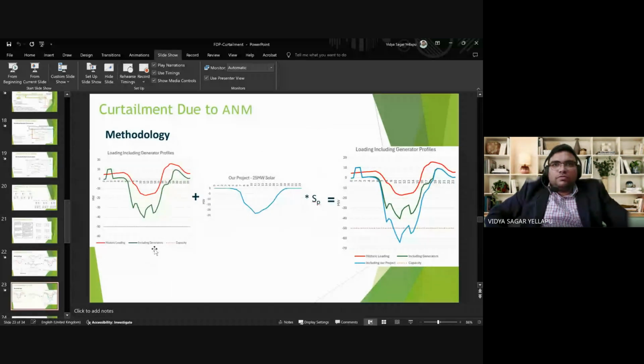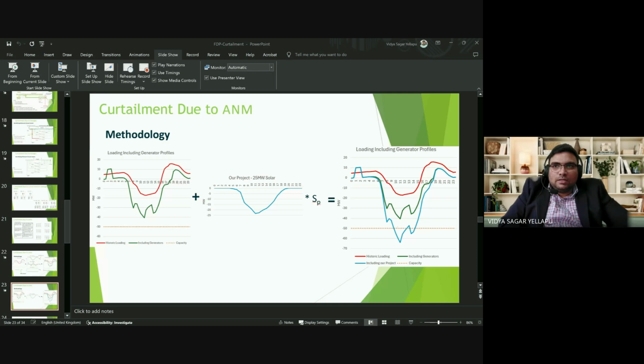Along with this, consider a new project of 20 megawatts size to be connected, with a sensitivity factor of 1 here for simplicity. In this case, it clearly exceeds this limit of 50 megawatts for this particular asset. In this case, all this generation in excess of this 50 megawatts is to be curtailed. So the generator will lose this much revenue.